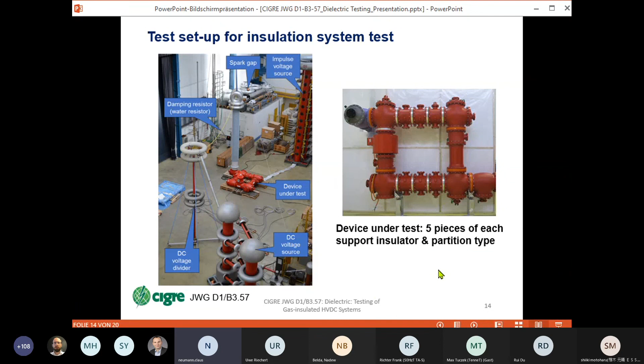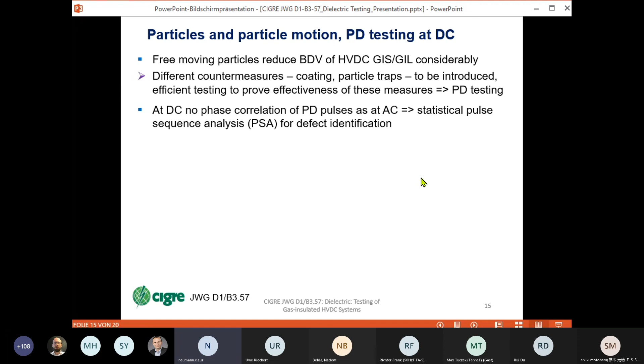Now, with regard to particles and particle motion, PD testing is of interest. As we have learned, free moving particles can reduce the breakdown voltage, and different countermeasures have to be applied. But there is no phase correlation of the PD pulses as given at AC, so we have to use other methods, the so-called statistical pulse sequence analysis for defect identification.